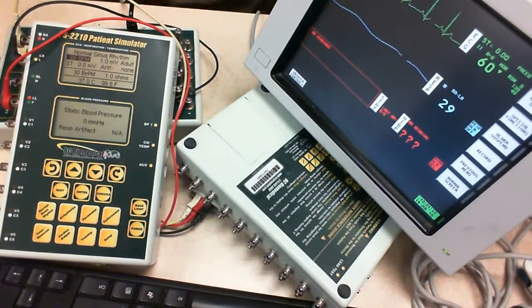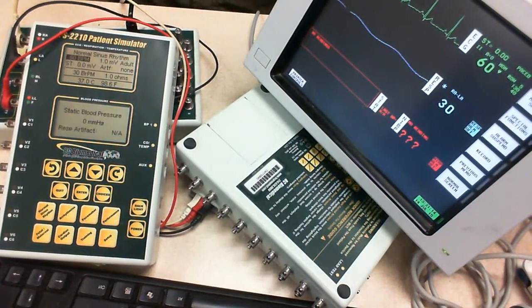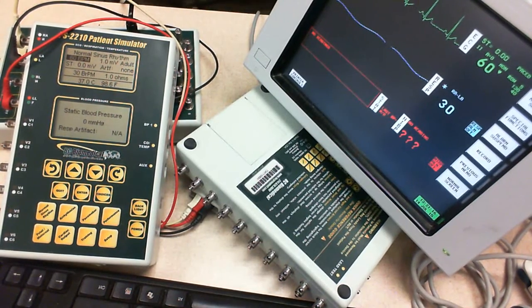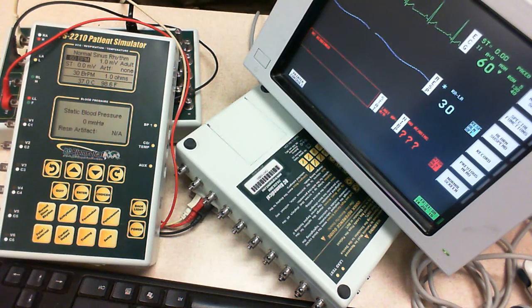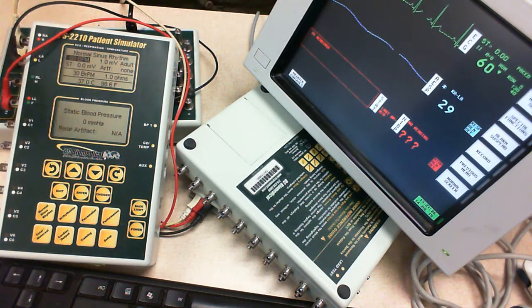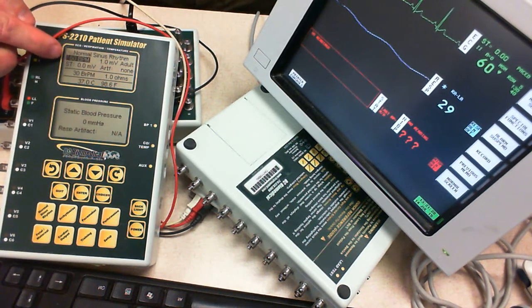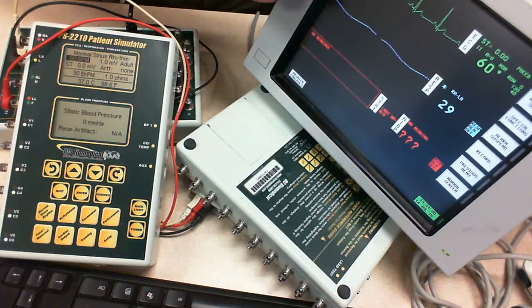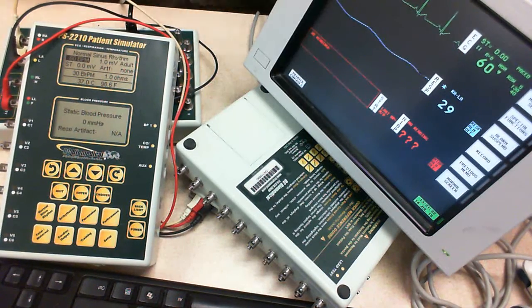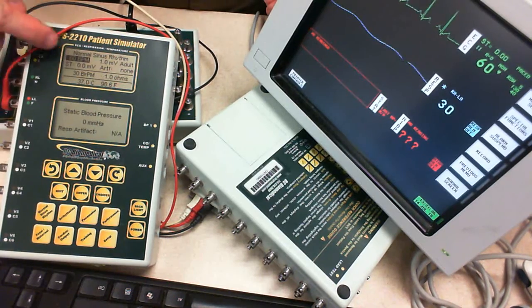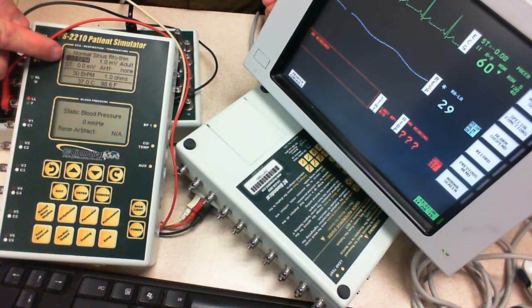People ask me, well, why not zoom in? Well, first off, I've got this large area to cover, and second off, it's putting it at a different level, and it's going to be a challenge. Anyway, moving along. Doing the rate calibration, we've got 60 beats a minute right here on my tester. I've got 60 beats a minute right here on my monitor, so that's a good check.